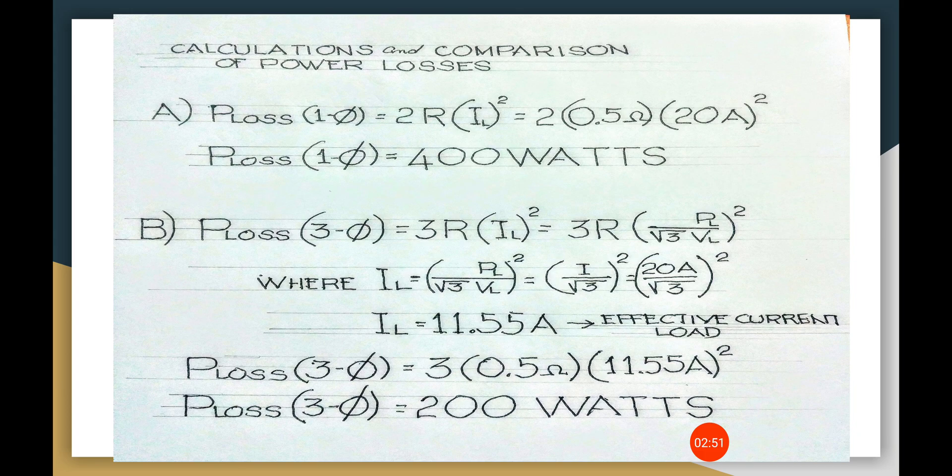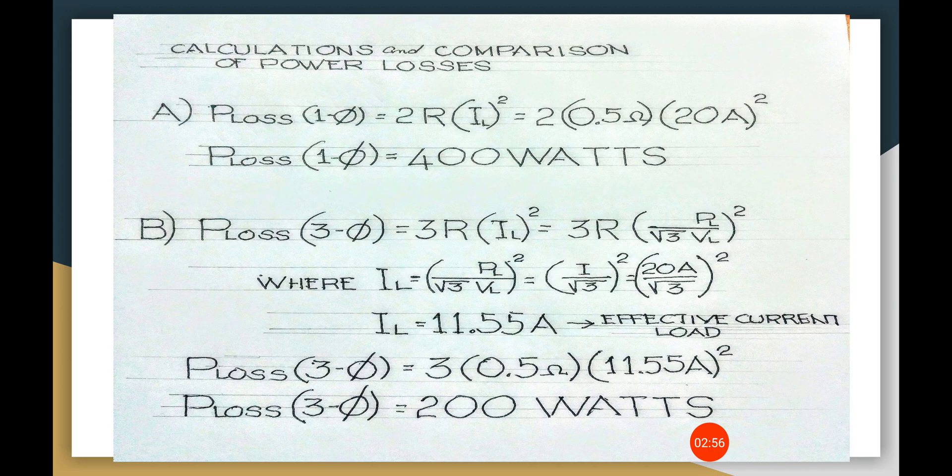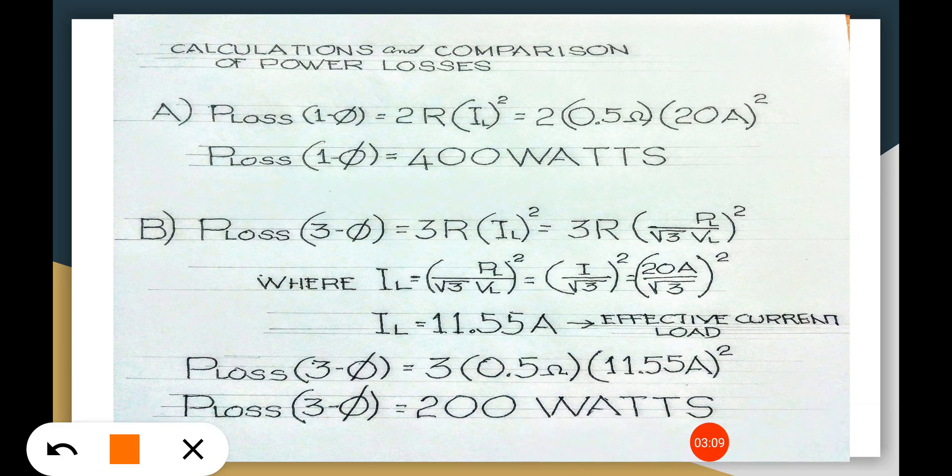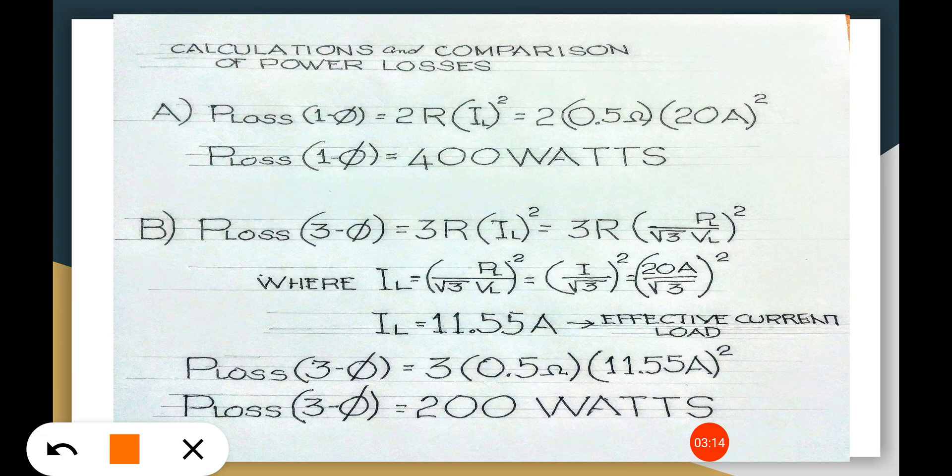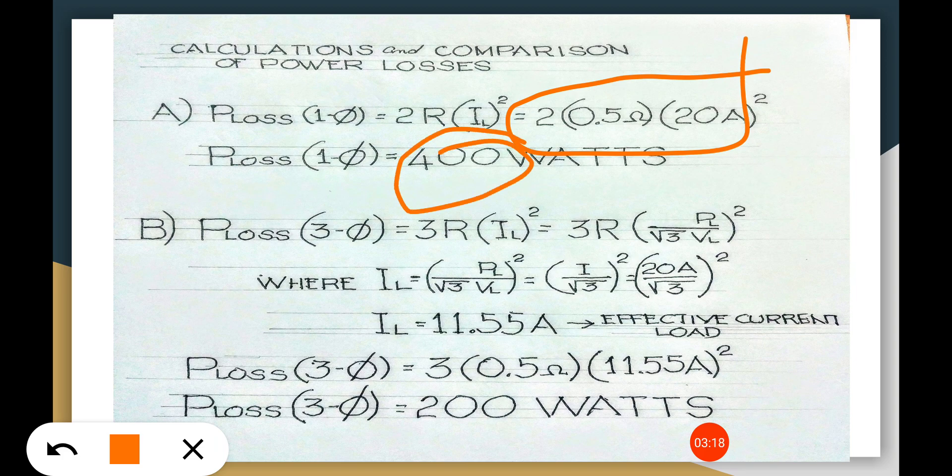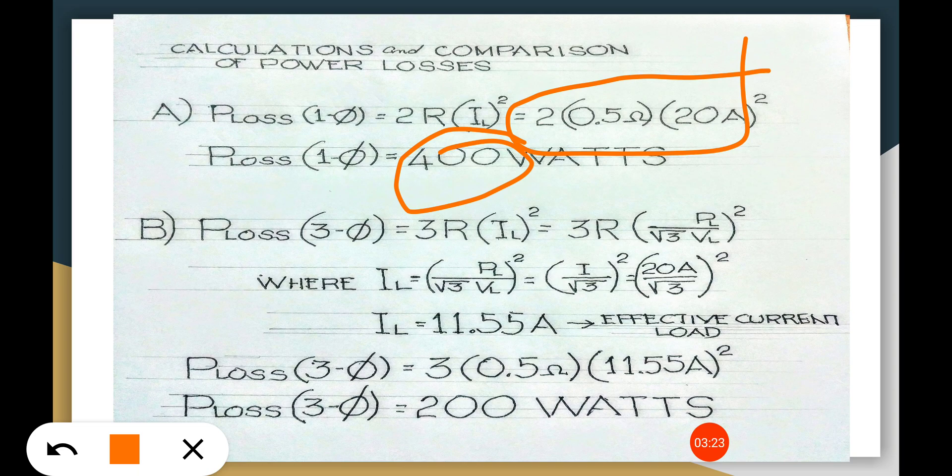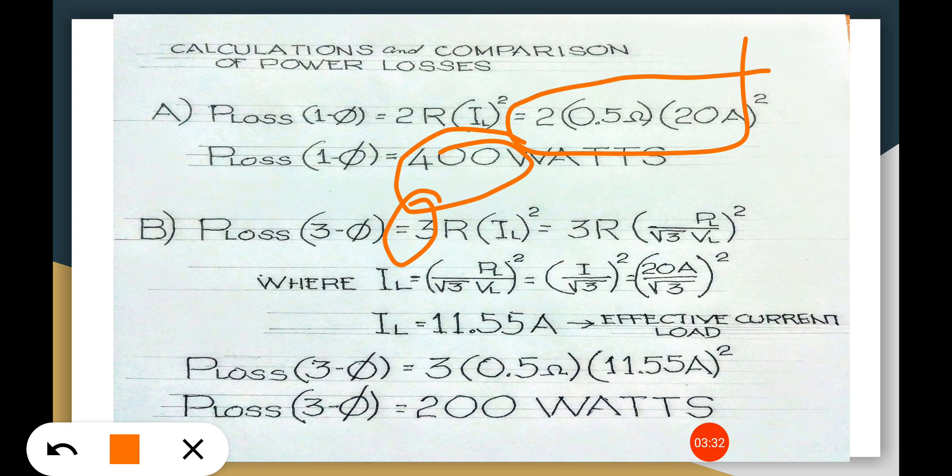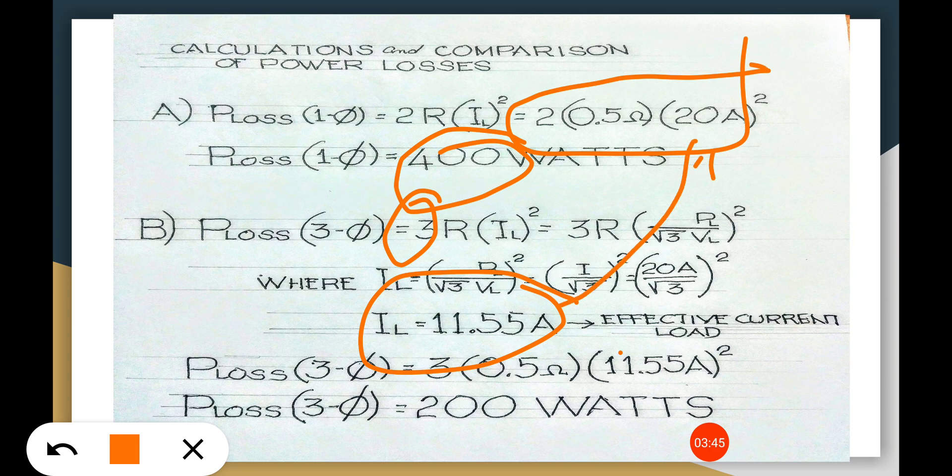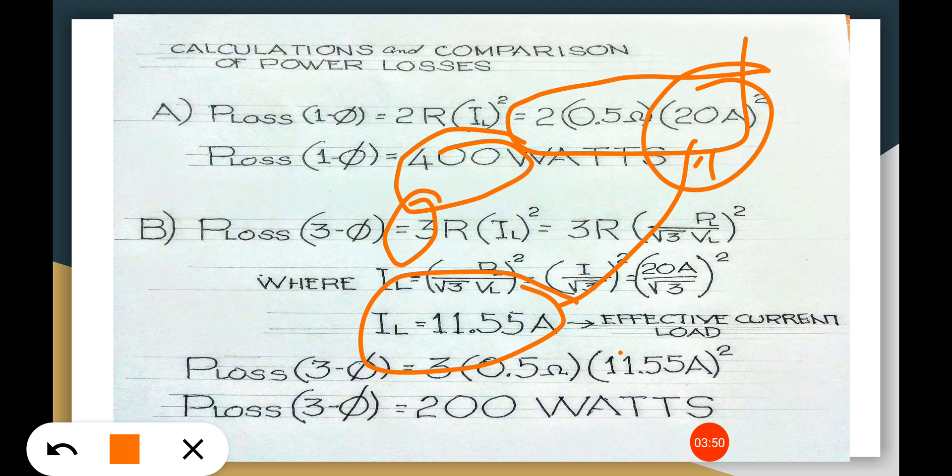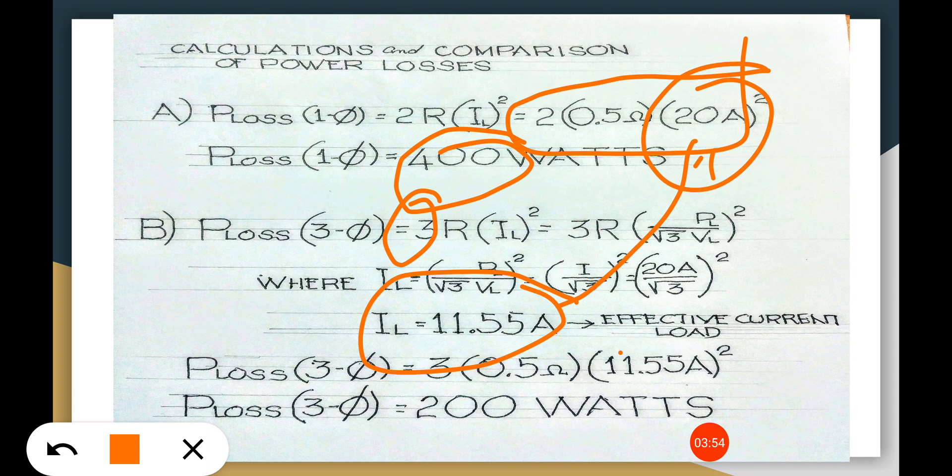So we go to the next one. We have this power loss, you just have to substitute the given ohms of resistance and amperes. And we have the ohms and our system is 4, we have two here because it's a two wire system. So we have this two, so this is the watts. And for the three phase system we have 3R I squared, the three because it's three wires, so we multiply this by three. And so we have this effective current load of 11.55A as compared to 20 amps, which has a significant reduction in the power loss of a three phase system, which is only 200 watts compared to 400 watts.